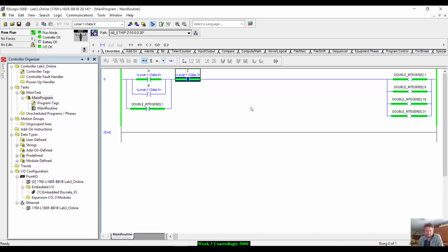Yes. Okay, as we can see now, A is on, and that is input 6. Apparently that's a normally closed as well. Okay, so I got to press that and it turns it off. And if I hit C, which happens to be bit 3, is also normally closed, that drops it out. I got 2 normally closed push buttons, so I got to press them both to get them to turn off. And if I want B to come on, I have to turn on C and press number 5, which is a normally open. And bam, there we are.